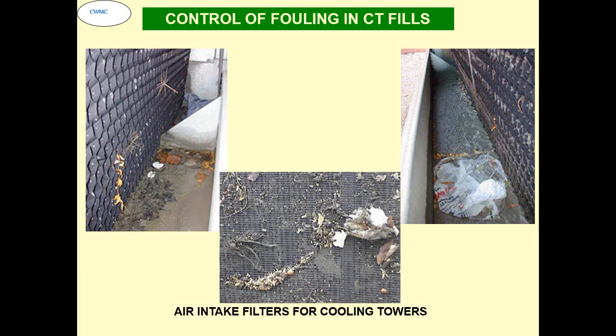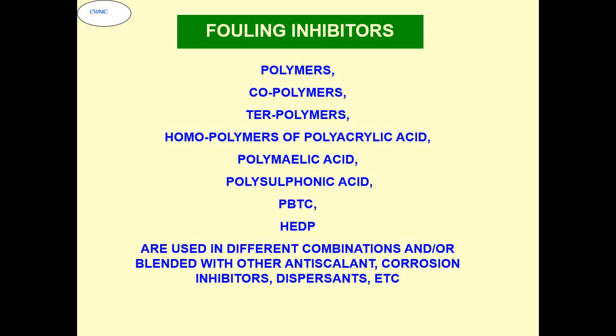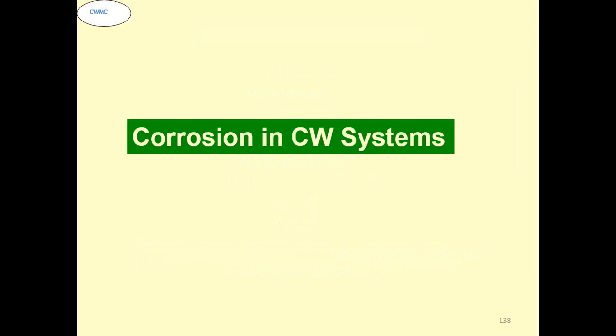In this case, the entire cooling tower is encased in filters, and all the air that comes through the cooling tower is first passed through the filter, and then it is pressurized and sent to the cooling tower. So that makes the system very expensive, but yes, it will keep the system clean also. There are certain inhibitors which are used for fouling, like polymers, copolymers, terpolymers, homopolymers of polyacrylic, polymaleic, polysulfonic, PBTC, HEDP, etc. They are all common fouling inhibitors, and many of them have an anti-scalant role also. Corrosion in CW system.